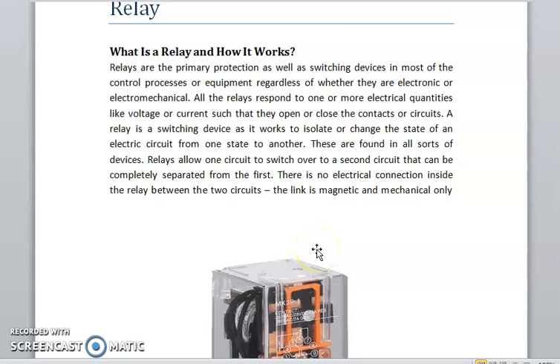Relay. What is a relay and how does it work? Relays are the primary protection as well as switching devices in most control processes or equipment, regardless of whether they are electronic or electromechanical. All relays respond to one or more electrical quantities, like voltage or current, such that they open or close the contacts of circuits. A relay is a switching device as it works to isolate or change the state of an electric circuit from one state to another.